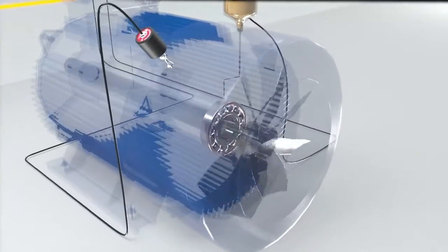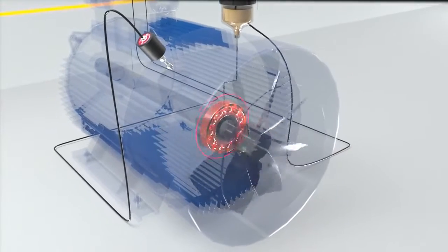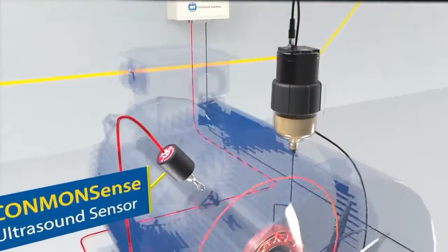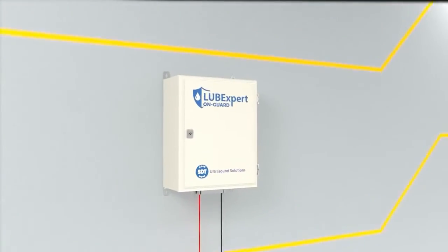When a bearing is suffering from increased friction, ultrasound technology allows us to hear these failures. The ConMon Sense sensors pick up these ultrasound signals and send them to the LUBExpert ON-GUARD.